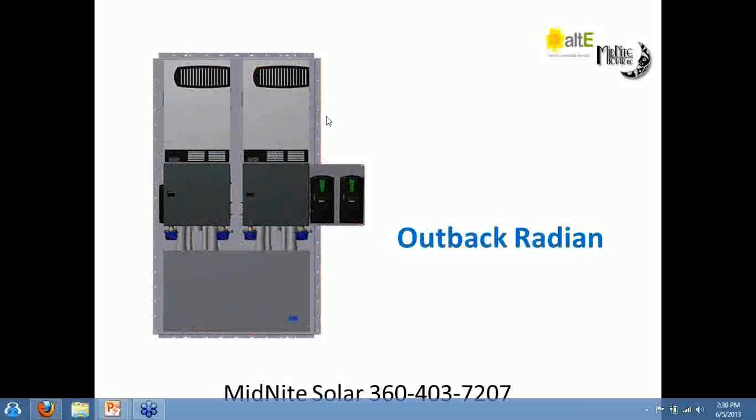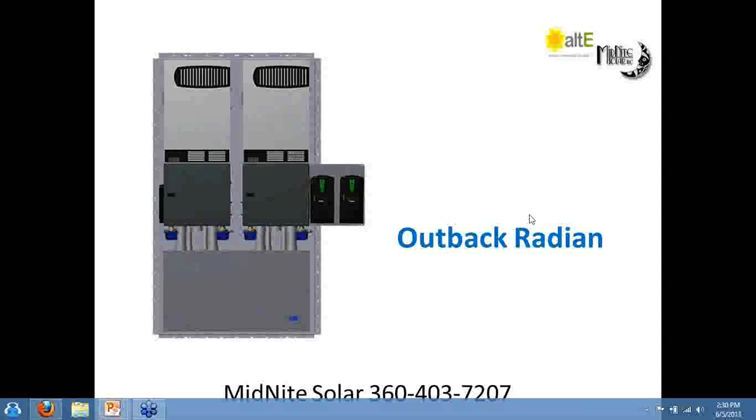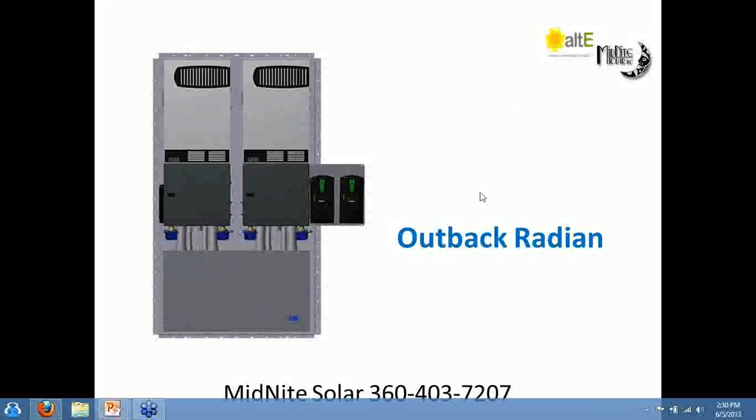It's probably about an hour-and-a-half project to wire those two together on site, but it makes it much more manageable to get it up on the wall. So again, we're very, very flexible in this scenario. We can wire these as a full complete package like this if you've got a way to get them on the wall, or we can break them up in pieces and do what I would call a semi pre-wired, which makes it a little bit easier to manage if you don't have quite as many people on site.